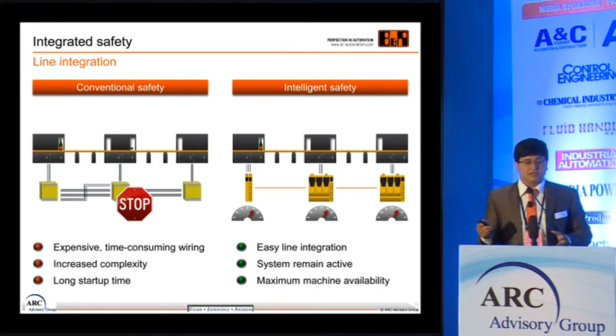So how can the intelligent, smart safety solution achieve this? You have a safety which is running. Suppose safety is violated because the operator needs to work on something. But instead of the plant going to shutdown, it goes to some safe limited speeds, where the operator can clear the hazardous part and clear the safety, but the other machines keep running at the lower speeds. So you are not losing productivity. Plus, once your safety is clear, your plant can directly ramp up to your maximum production speeds. So the intelligent safety gives you a way to handle productivity and also safety. So both are being achieved.